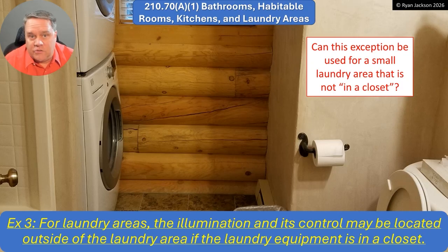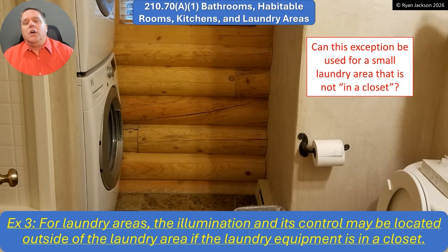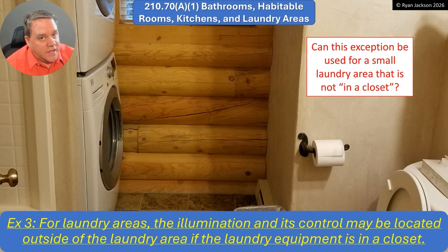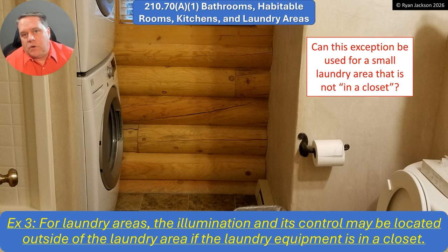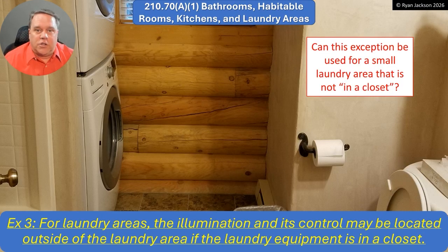We added a new exception here, which I think is a good thing. For laundry areas, the illumination and its control may be located outside of the laundry area if the laundry equipment is in a closet. This used to say bathrooms, habitable rooms, and kitchens. Then in the 2023 code, we added laundry areas. The laundry area needs illumination — it needs a lighting outlet. But what if your laundry equipment is a stackable unit in a little closet off the hallway? Do you really need a lighting outlet in that closet? And what would it even do? It's probably going to be above the dryer — you turn it on and it doesn't even illuminate anything. It would just add heat and maybe even be a fire hazard.